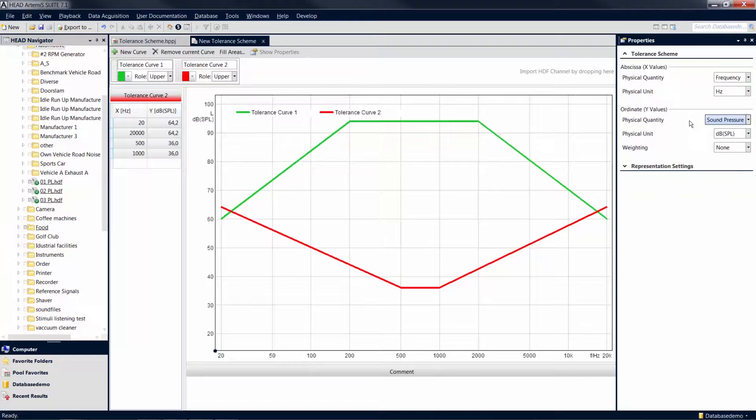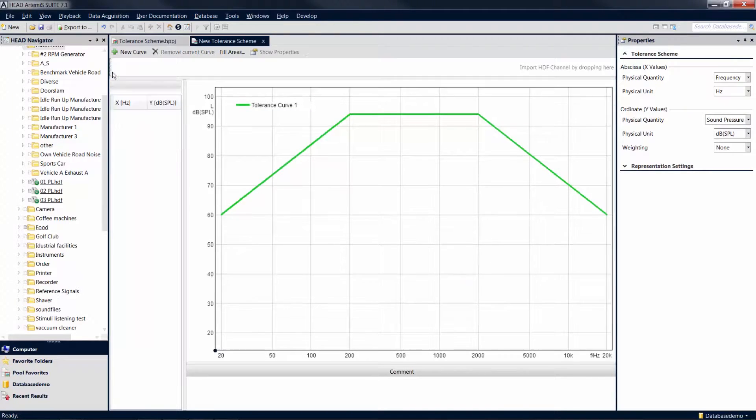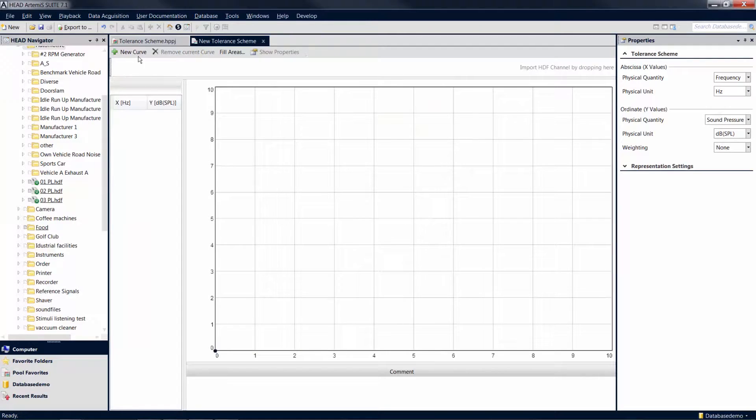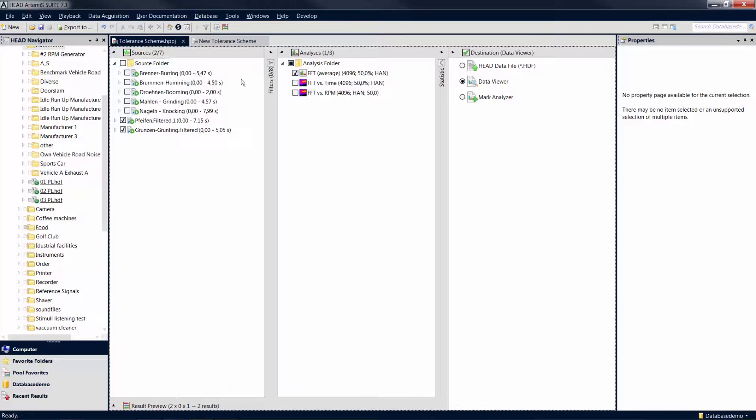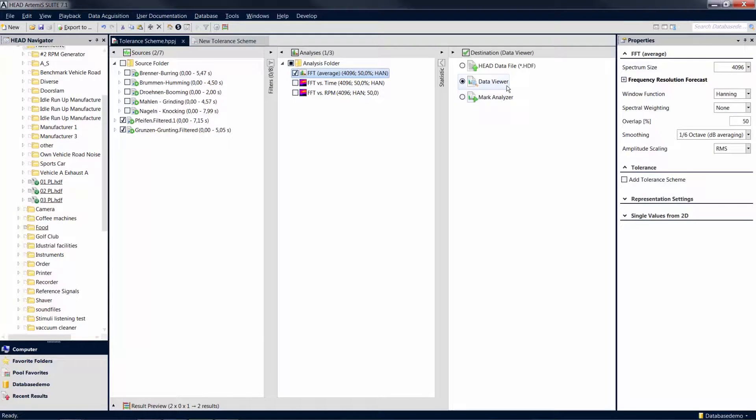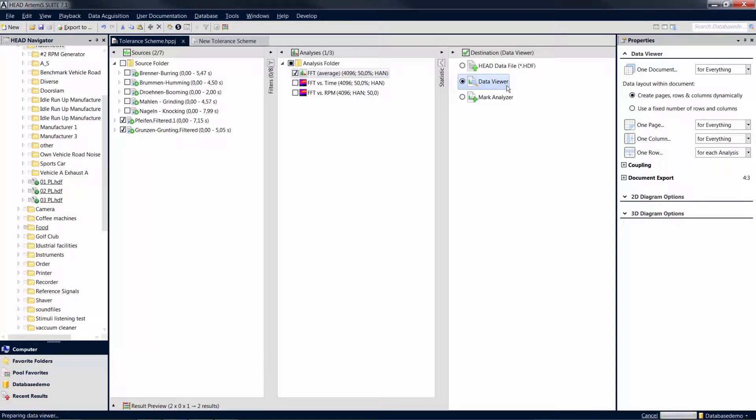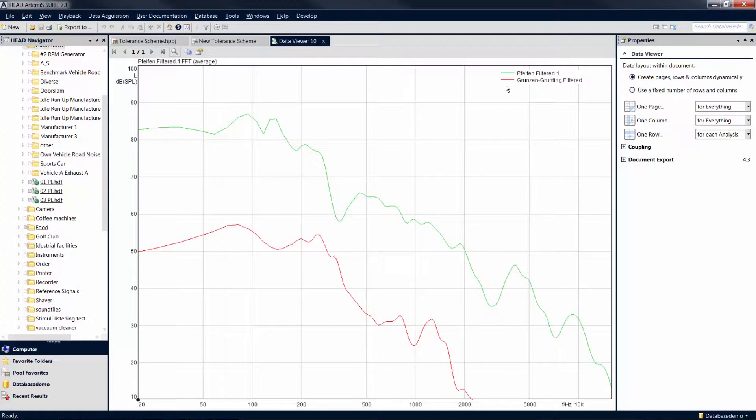You can create the curves for a tolerance scheme not only by entering numeric values, but also by using the results of previously calculated analyses. For this purpose, we first calculate the FFT average analysis of two marks with a data viewer as the destination element. For this application case, we only need one channel of each respective mark. These two result curves are now to be used as the upper and lower tolerance limit curves for a new tolerance scheme.